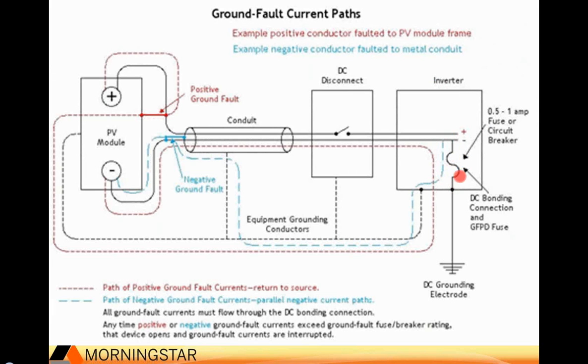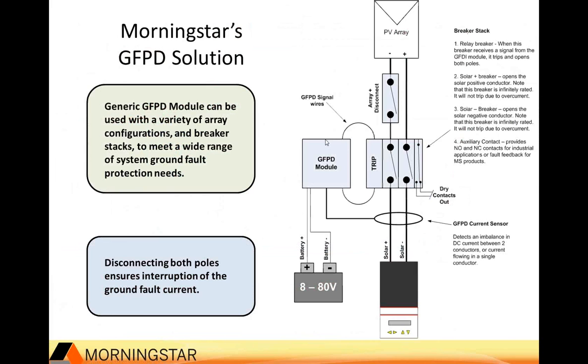What it does is this provides a current path for the ground fault. So the ground fault has to actually occur and provide current flow through this bond when it's trying to return to the negative. Okay, upon breaking this, that's when the ground fault is detected and tripped. But there are a lot of weaknesses in this type of solution, and that's what I'm going to talk a little bit about because we're proposing a different way of doing this.